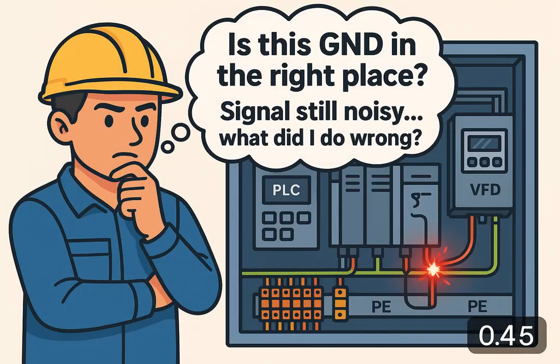Have you ever had a perfectly wired analog sensor, shielded cable, stable 24-volt power, PLC working fine, but the analog reading keeps jumping, drifting, or shaking? You check the wiring. Signal plus goes to the correct AI plus terminal. You use shielded cable. Power supply is stable. Everything looks perfect on paper, but the signal is still full of noise.